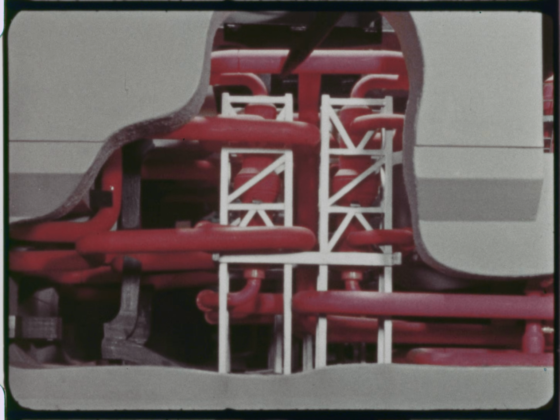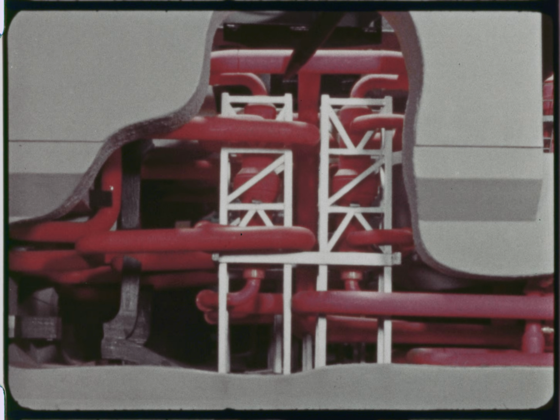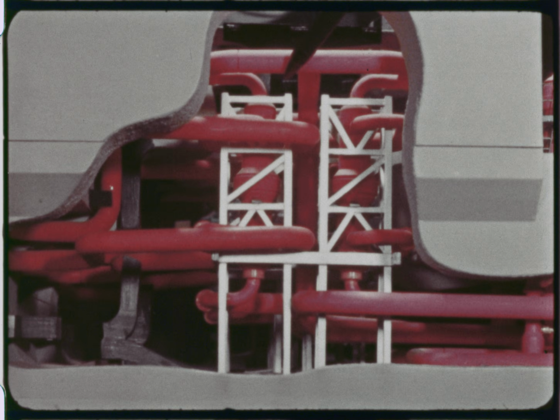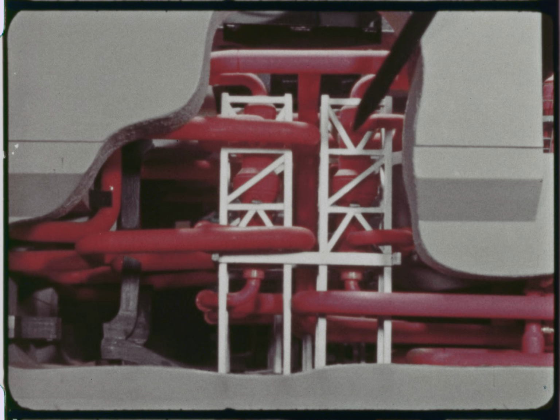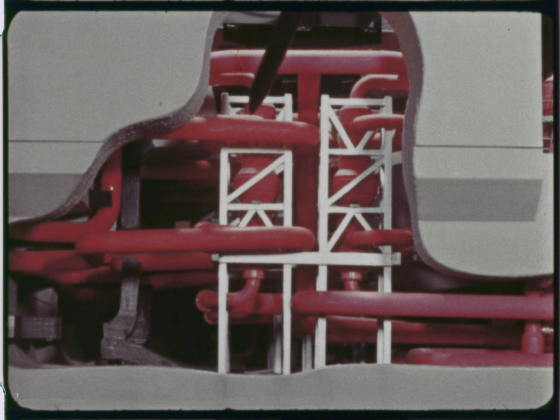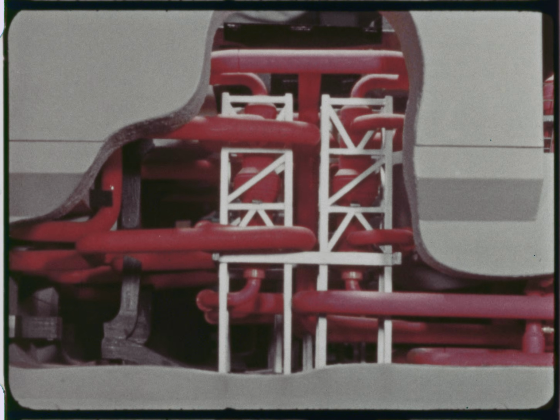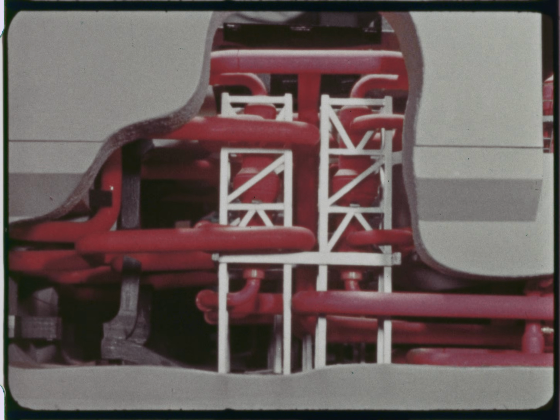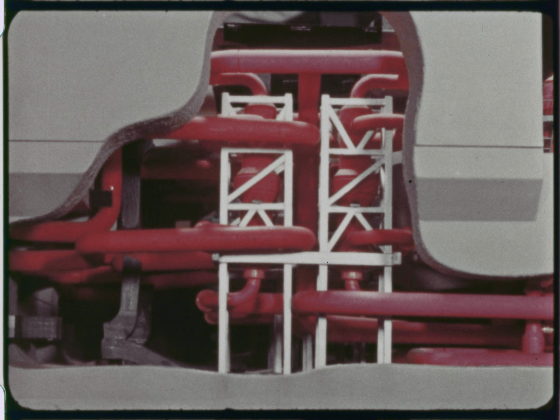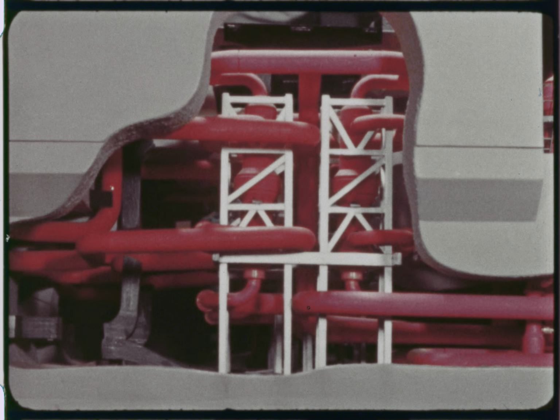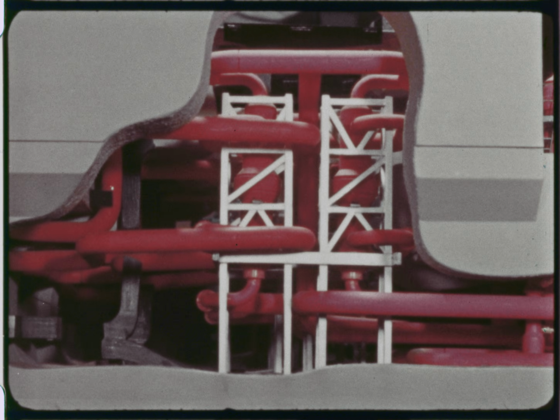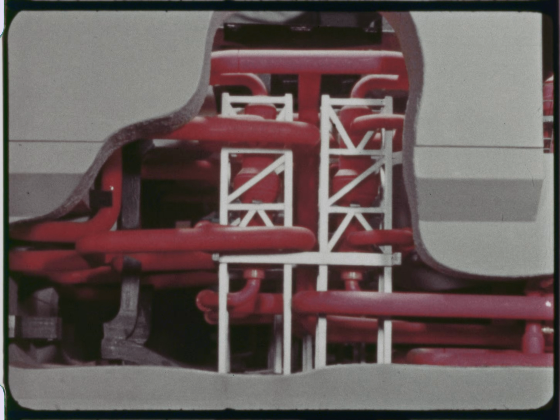The use of an intermediate heat exchanger is required because the sodium becomes radioactive in passing through the reactor core. Each intermediate heat exchanger is made up of 2 units operating in parallel. Each unit is of the shell and tube counterflow design, with the primary sodium contained in the tube side. The stainless steel exchangers are mounted vertically in the heat exchanger cell.